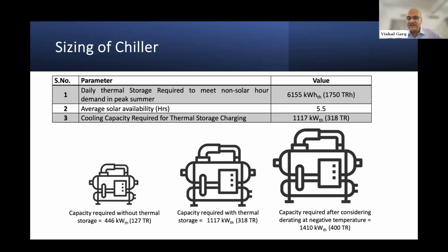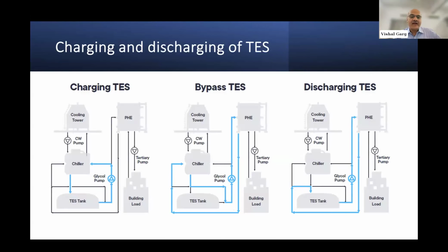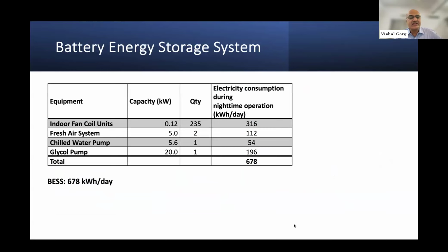So that is the chiller we installed, and it can work in 3 modes. It can be in a mode where it is charging the tank. It can be in a mode where it is directly supplying cooling to the building without charging. And the third is it is discharging the tank and providing cooling to the building. That will happen in the night time. So we have this system and it is being commissioned.